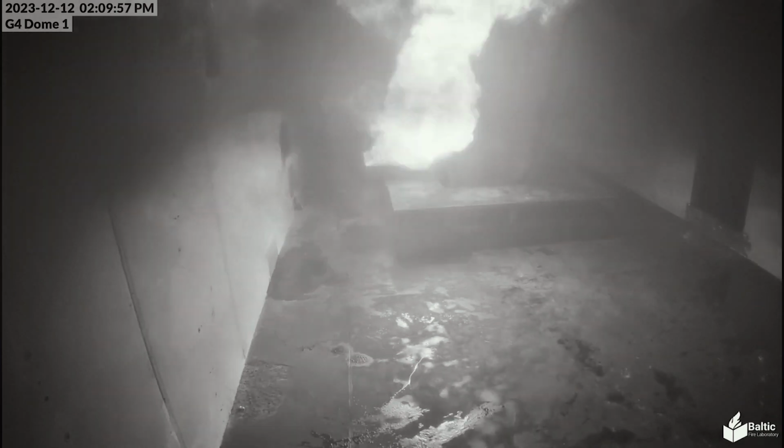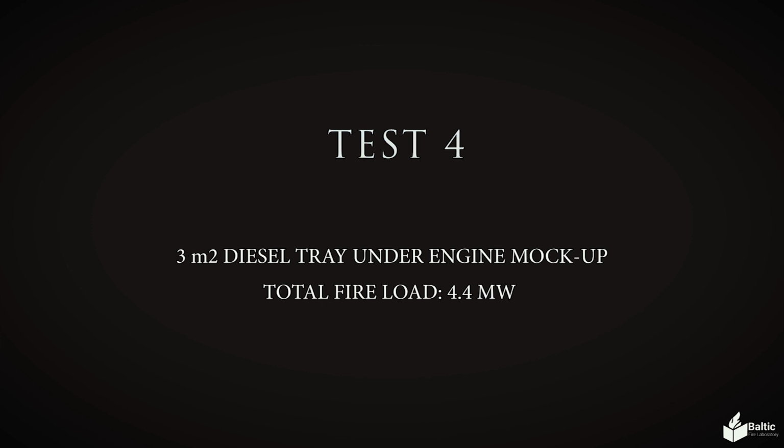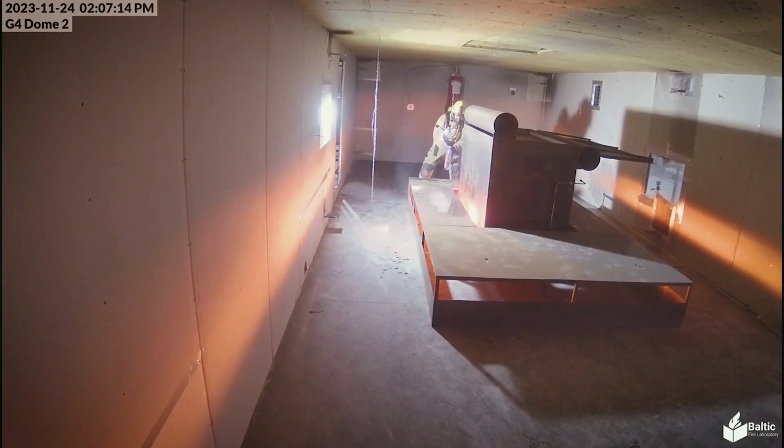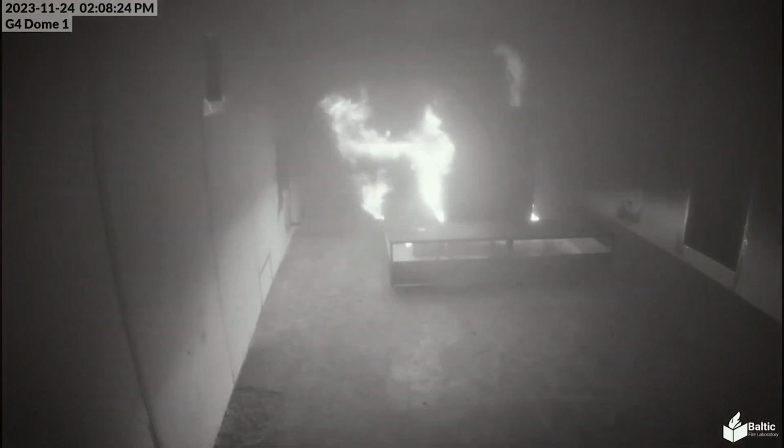20% oxygen before the release of the system. When we closed all the openings and released the system, we observed plus 250 pascals of overpressure in the enclosure, and within milliseconds minus 250 pascals. In one of the tests we completely damaged the enclosure because of this effect. In this test you can see on the cameras the whole wall of the enclosure just flexing. So if someone is using a gas system, they should take this overpressure seriously.